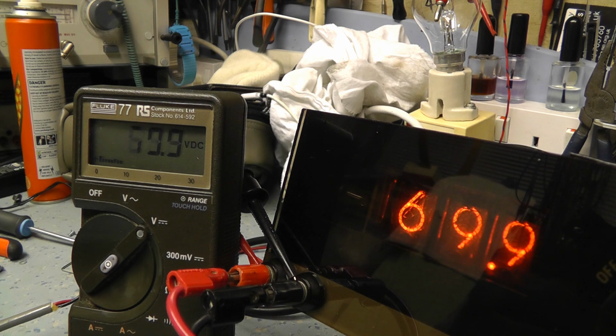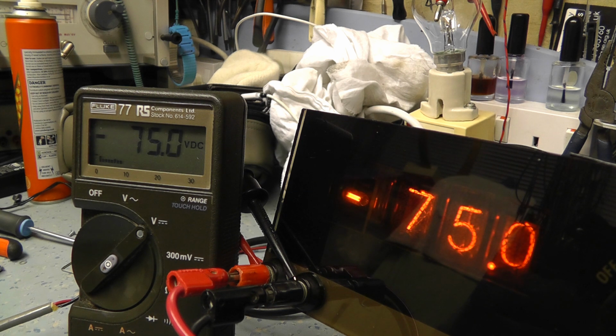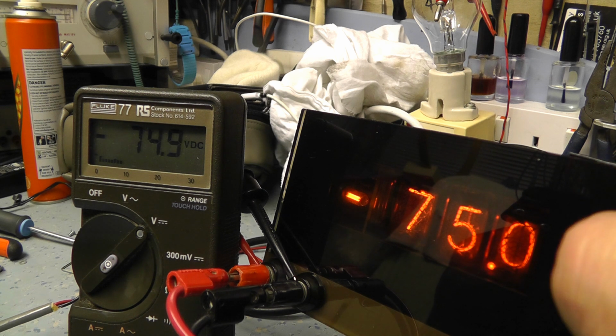75. That's 75 volts. So we've got 74.9 on the Fluke. Got 74.9 on the Roband. Minus 75, minus 75. That's excellent. It's really much better results than I was getting. I tried everything on the actual input attenuator and the amplifiers, and I couldn't get that to balance. But now I've adjusted that reference up slightly, I've managed to pull it all in. See, the references have drifted, something altered it over time.